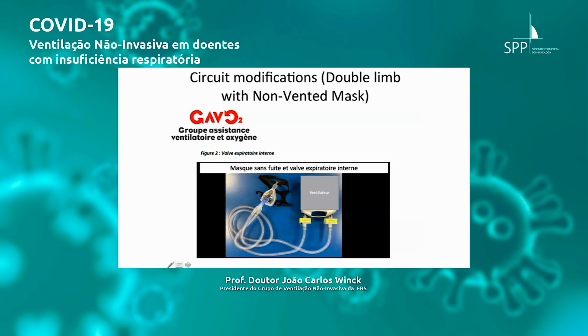This kind of setup is useful because not all our common ventilators have the possibility of a dual limb. In this case, this ventilator has this possibility, and so here you have two filters, one on the expiratory and another on the inspiratory limb, and then finishing with the blue elbow. If we have this configuration of double limb without any intentional leak, what would you say? Is this safer? Is it better than the other solution?